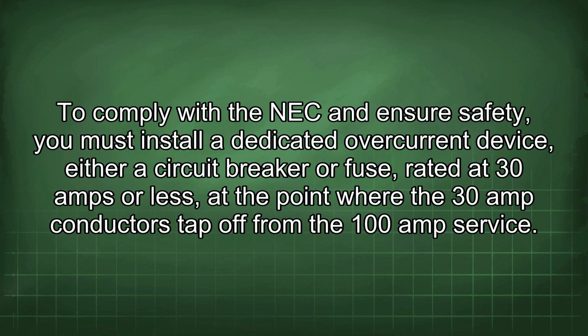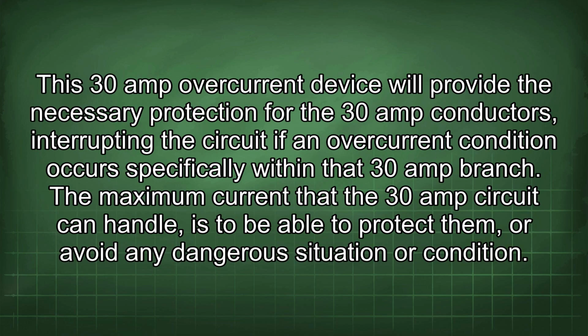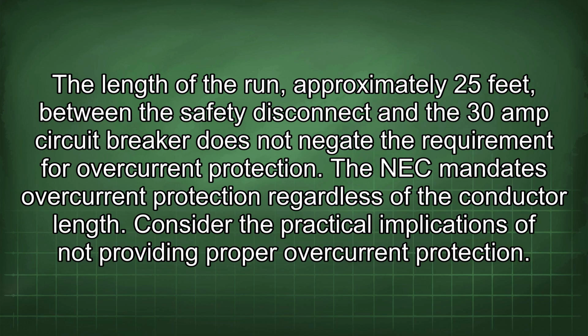To comply with the NEC and ensure safety, you must install a dedicated overcurrent device, either a circuit breaker or fuse, rated at 30 amps or less, at the point where the 30 amp conductors tap off from the 100 amp service. This 30 amp overcurrent device will provide the necessary protection for the 30 amp conductors, interrupting the circuit if an overcurrent condition occurs specifically within that 30 amp branch. The maximum current that the 30 amp circuit can handle must be respected to avoid any dangerous condition. The length of the run, approximately 25 feet, between the safety disconnect and the 30 amp circuit breaker does not negate the requirement for overcurrent protection. The NEC mandates overcurrent protection regardless of the conductor length.